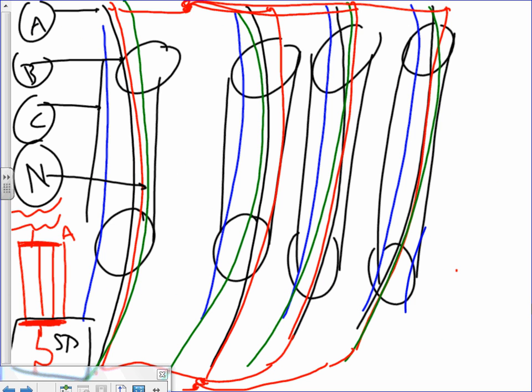Okay, all right, gentlemen. This is how you parallel. This is your paralleling. The first one, can you guys see the first one: phase A, phase B, phase C, neutral. In each one of these conduits, you will have phase A, phase B, phase C. Black, red, blue. Typically, the phases for a 208/120 system. And white, I can't write white on white here, so I put green here. So white will be your neutral. So these are how you parallel.